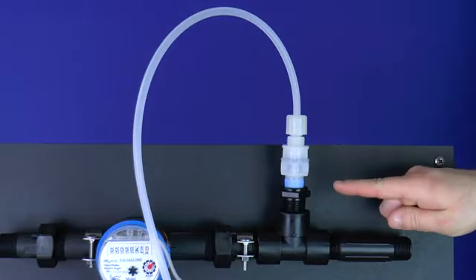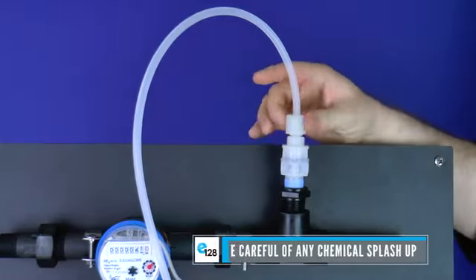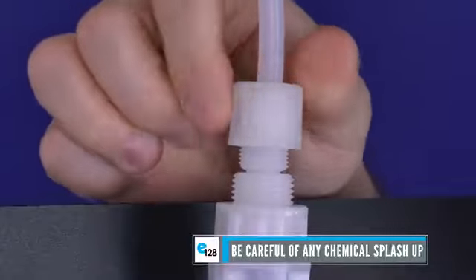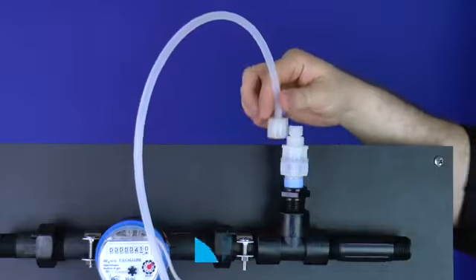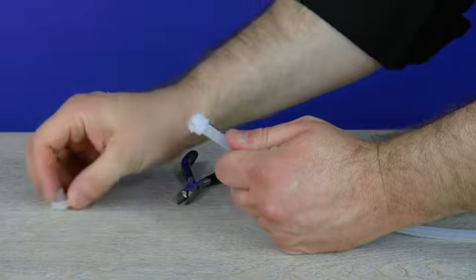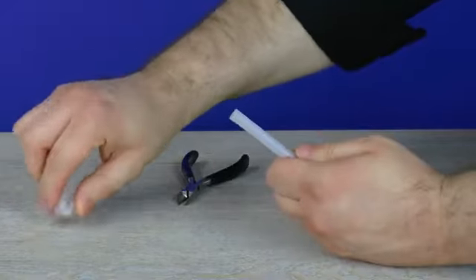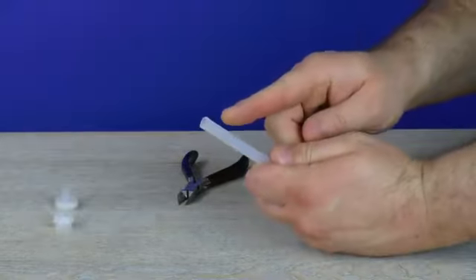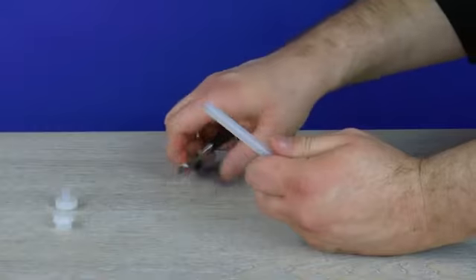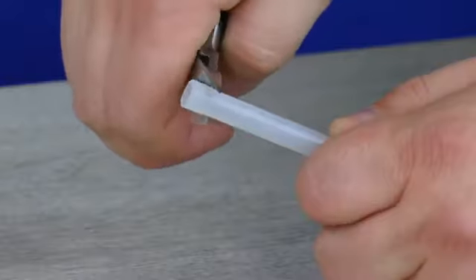Injection valve. Next, locate the injection valve in the supply line. Loosen the injection valve and disconnect the discharge tube, nut, collar, and nozzle attached. Remove the nozzle and collar from the tube and set aside. Do not lose them. Look at the end of the tube. If the tube's end is flared, use diagonal pliers to cut the flared portion off.